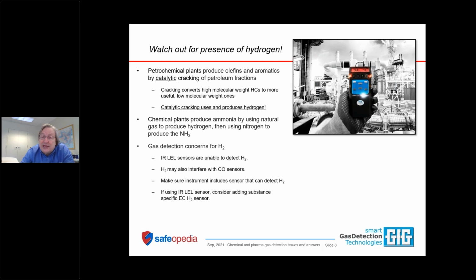So that means that if you have, say, 1% LEL hydrogen, which would be a concentration of 400 parts per million, you're going to get a reading of 5% of 400. So, that's quite a bit of hydrogen. That's going to look like you have that on the CO channel. You're going to be in alarm for carbon monoxide if you're setting it at the permissible exposure limit.